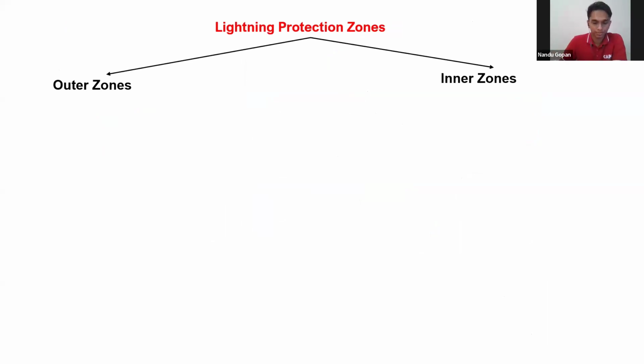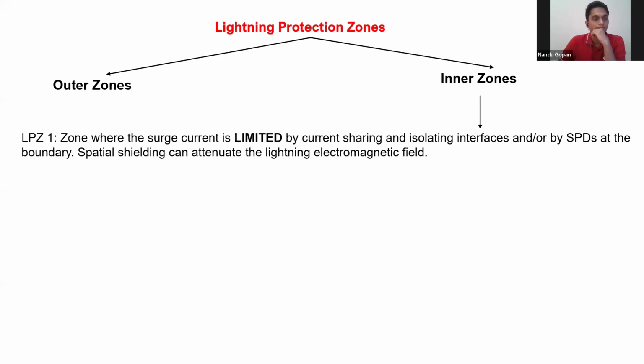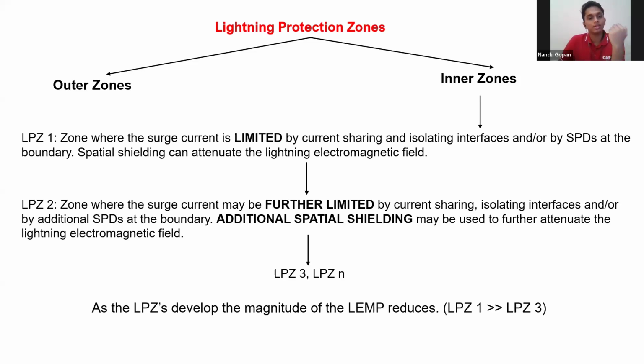Now, if you go to the inner zones, inner zones are classified into LPZ1, LPZ2, and LPZ3. It can go till N. Now, why are we saying so? In zone 1, you will be getting some limited surge currents, and that will be reduced by some SPD. From zone 0 to zone 1, you will get some lightning current, but that will be reduced by some SPD. In zone 2, you'll still be getting some lightning current or magnetic field, but it will be lower than zone 1. And in zone 3, you will still be getting it, but it will be lower than zone 2.